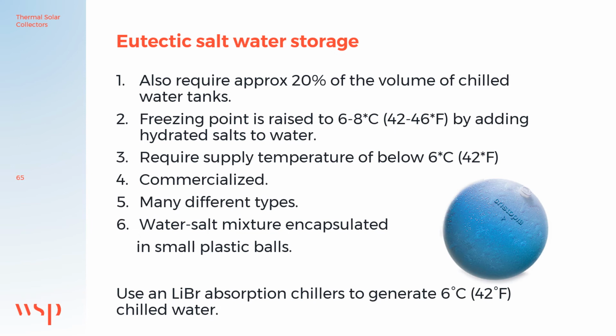Eutectic saltwater storage is another alternative to ice storage, and it requires only 20% of the water volume of a typical chilled water tank. However, the freezing point is raised to 6 to 8 degrees Celsius or 42 to 46 degrees Fahrenheit by adding hydrated salts to water. The water-salt mixture is encapsulated in small plastic balls, and the system requires a supply temperature of 6 degrees or 42 degrees chilled water. These types of systems are also commercialized. The free heat from the solar collectors drives a lithium bromide absorption chiller to generate the chilled water for these tanks.